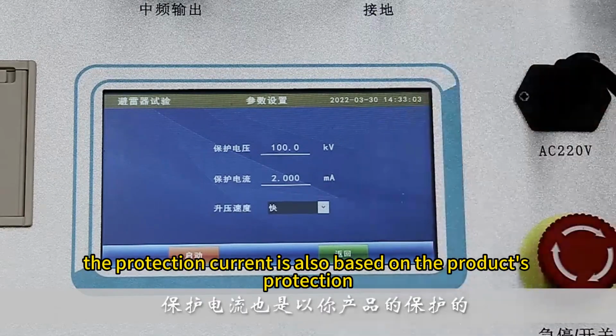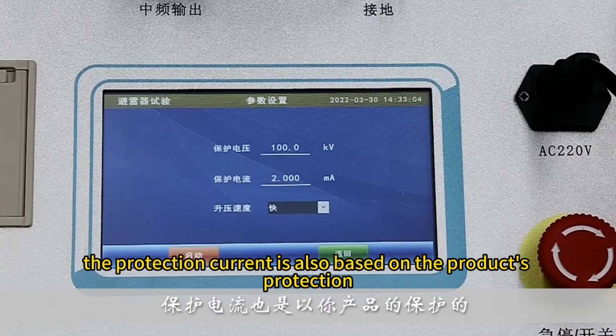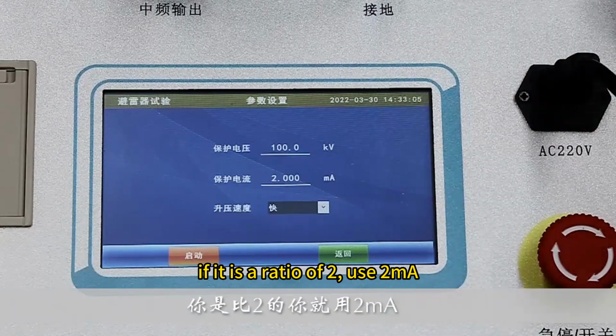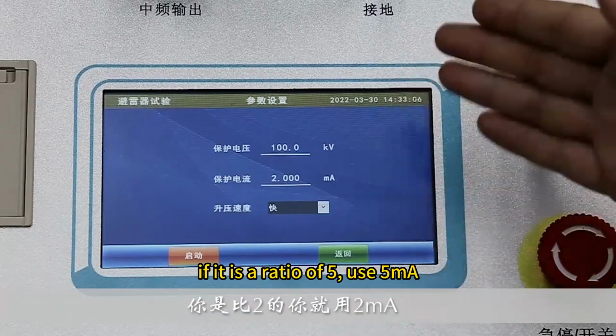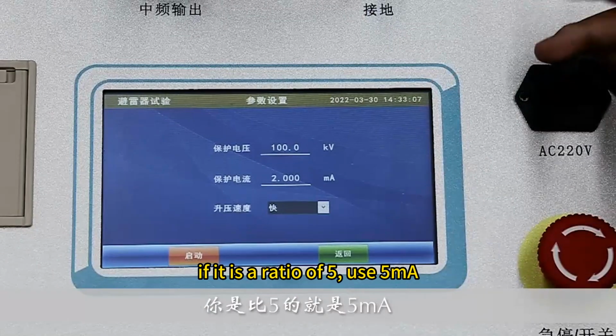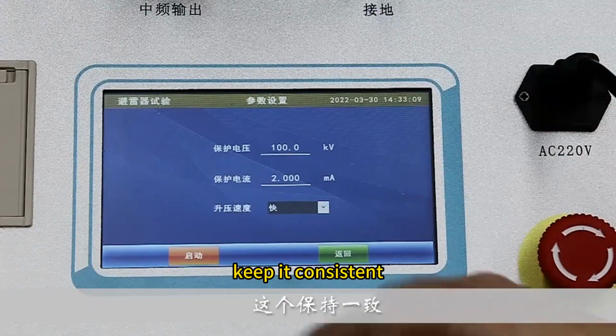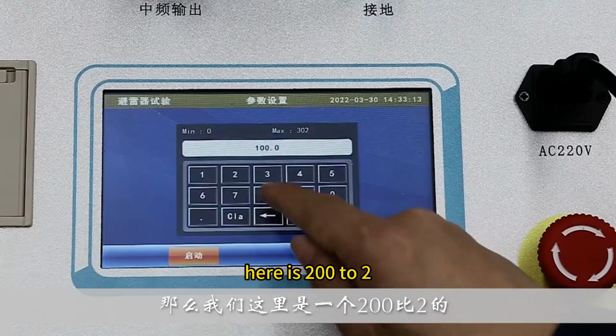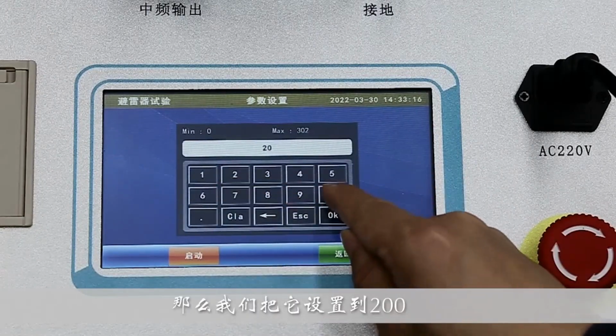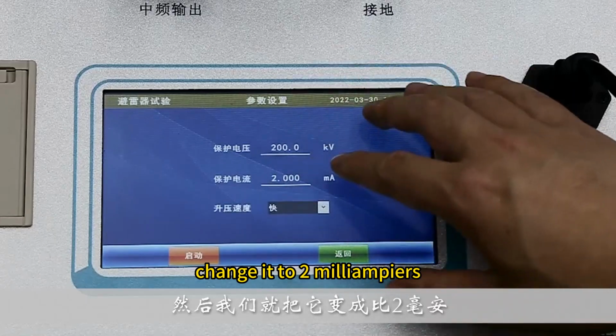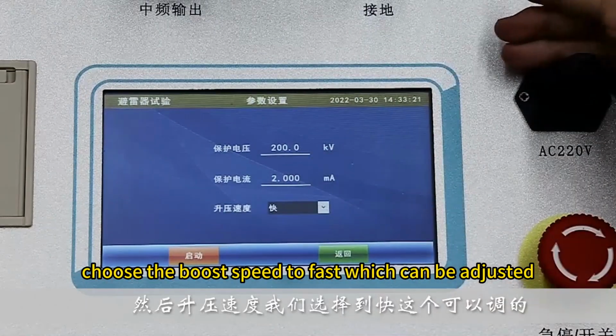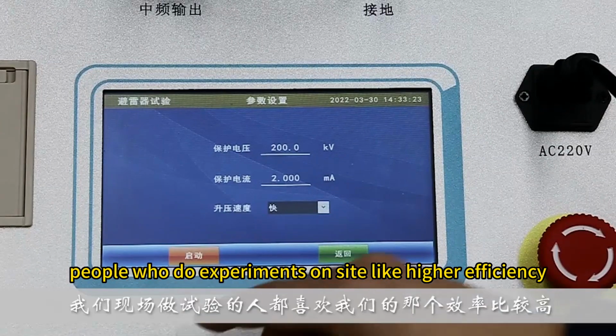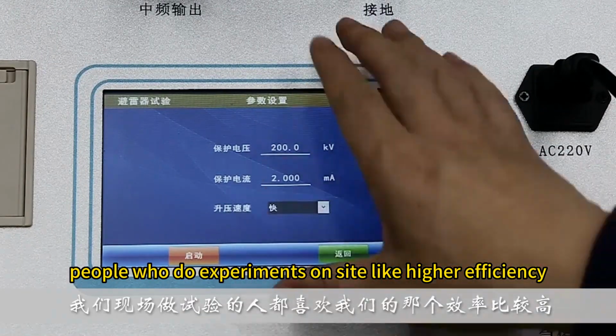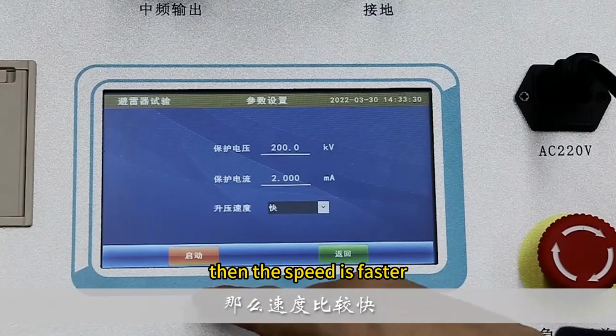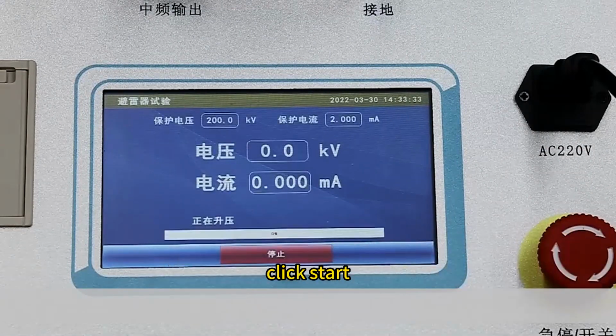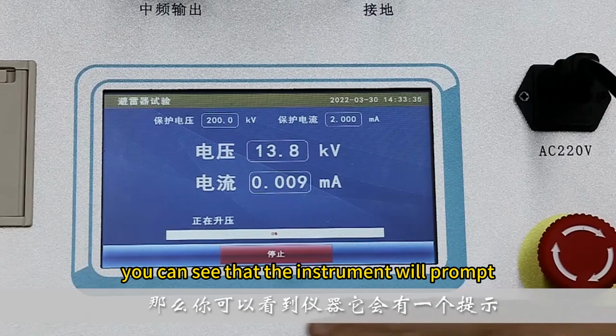The protection current is also based on the product's protection. If it is a ratio of 2, use 2 mA. If it is a ratio of 5, use 5 mA. Keep it consistent. Here it is 200 to 2. Set it to 200. Change it to 2 mA. Choose the boost speed to fast, which can be adjusted. People who do experiments on site like higher efficiency, so the speed is faster. Click Start. You can see that the instrument will prompt.